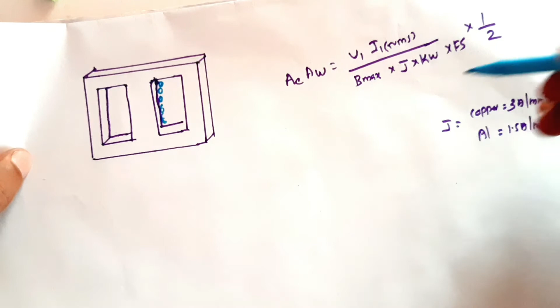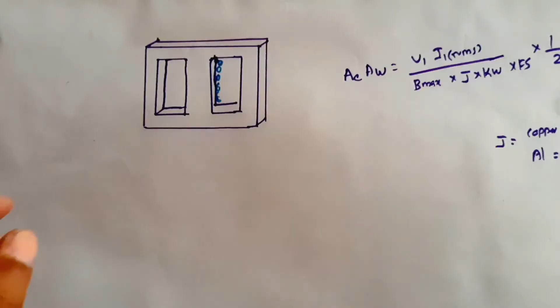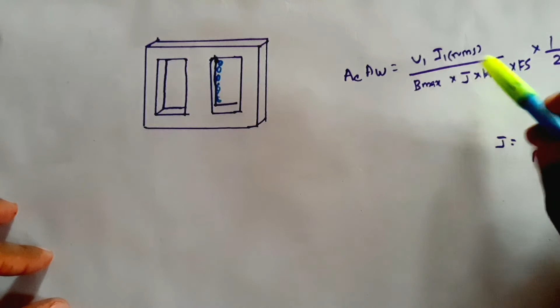KW means that if we wind more wires on it, more number of layers are needed, and each has to be insulated by an insulating material. As KW becomes low, more window area is needed.